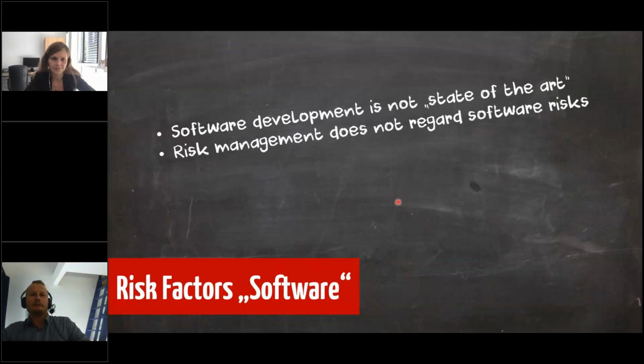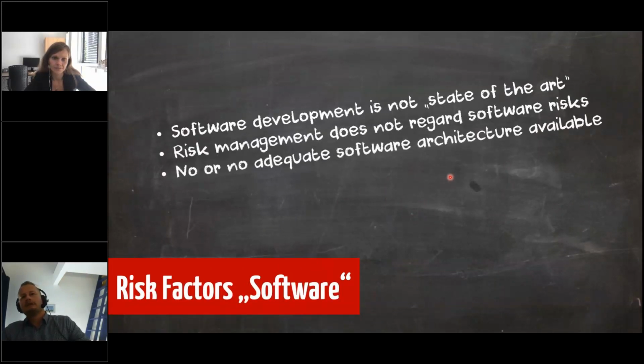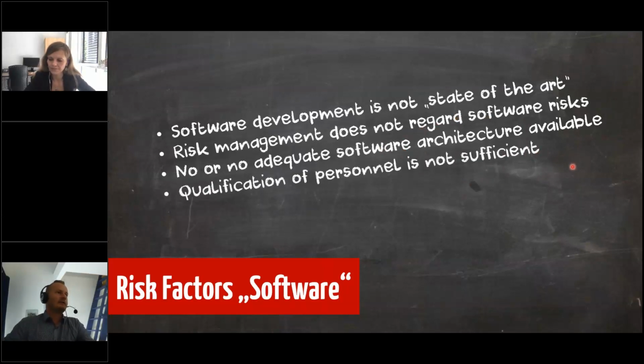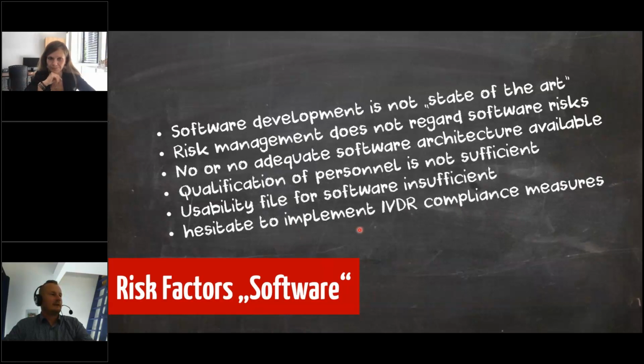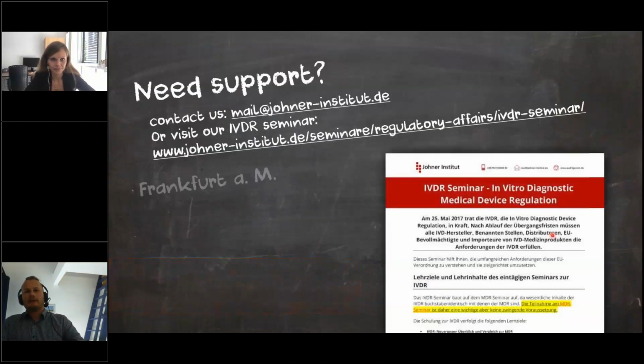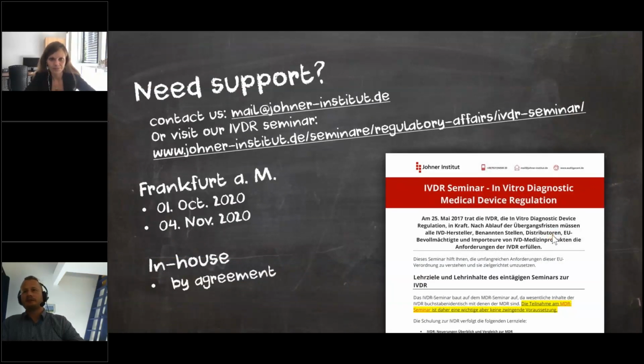Yeah. So just to give you a few risk factors for software. If software development is not state of the art, this is very crucial. Risk management does not regard software risks. This is very critical. No adequate software architecture available is for sure a major deviation to IEC 62304. And if you don't have a sufficient qualification of your personnel, you will certainly get stuck in showing compliance. And if usability for software is insufficient, that is very much a problem. And if you hesitate to implement IVDR compliance measures, that is what Michael already pointed out. This is one of the most crucial risk factors. So I'm at the end of my talk. If you need more help, contact us, and thank you for listening.